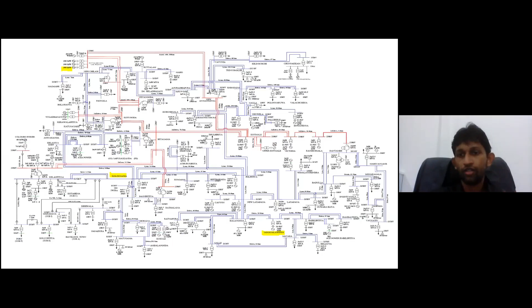Now, this is the national system in a very abstract manner. We have three 275 megawatt generators, and the load center is Kelowna. We did four simulations actually. In one simulation we had solar penetration, with the 400 megawatt of load, and we looked at the frequency when 275 megawatt of generation is being rejected.